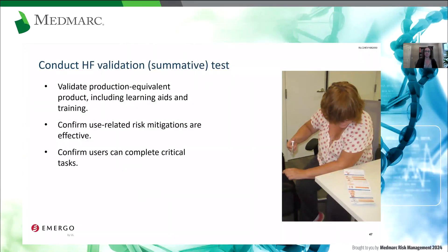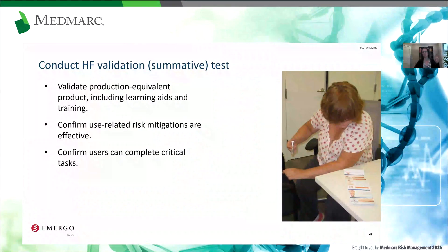When you come to a human factors validation test, you're looking to generate data to submit to the FDA or another regulatory body, showing that your risk mitigations — those risk control measures — are effective. You want to make sure that participants who are representative users of your product can perform critical tasks safely. For this study, whereas formative evaluations can have early prototypes, screenshots, printouts, or any kind of mock-up, the validation study — called summative in European guidance and standards — needs to include the production equivalent product. Ideally, in contrast to doing several formative studies, you do one validation study, because you've done your homework, revised the product design, and you're going in confident that the product can be used safely and effectively.